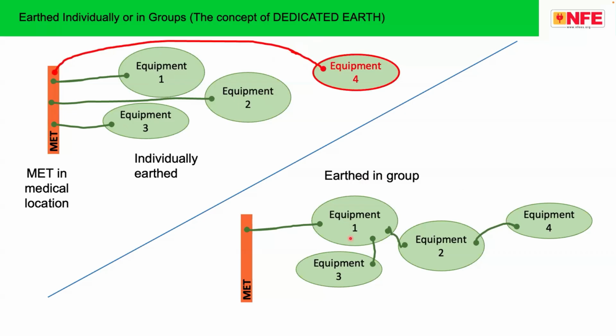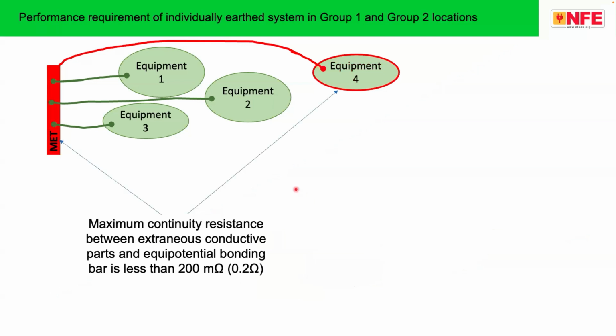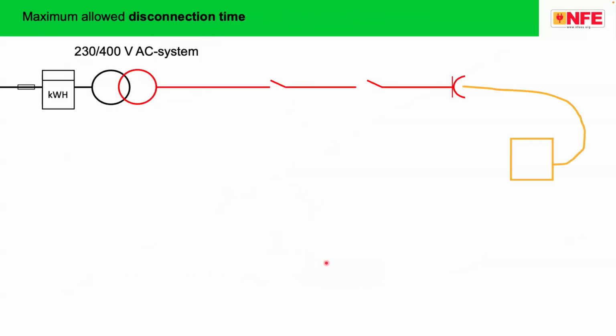The problem is, in an individually earthed system, if there is a leakage in equipment number 4, it does not influence equipment number 1, 2, 3. Whereas in case of group earthed equipment, a fault in equipment number 4 will influence equipment number 1 and 2. In order to avoid that, individually earthed systems are required, and the maximum resistance between the MET, common bus bar, and the individually earthed systems is also specified in the standard. Please note that earthing has nothing to do with the earth pit, plate, pipe in the system.